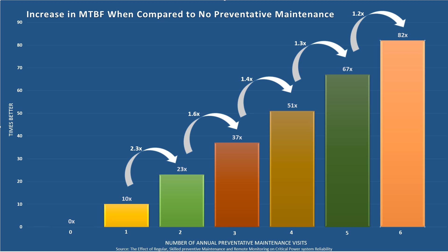This study showed the following results. Looking at this curve, it compares scheduled maintenance on equipment using online monitoring. If you do just one inspection a year and install online monitoring systems, you can increase MTBF by up to 10 times. Do 4 inspections a year and we can increase MTBF by 51 times, and with 6 inspections a year, we can increase it by 82 times.